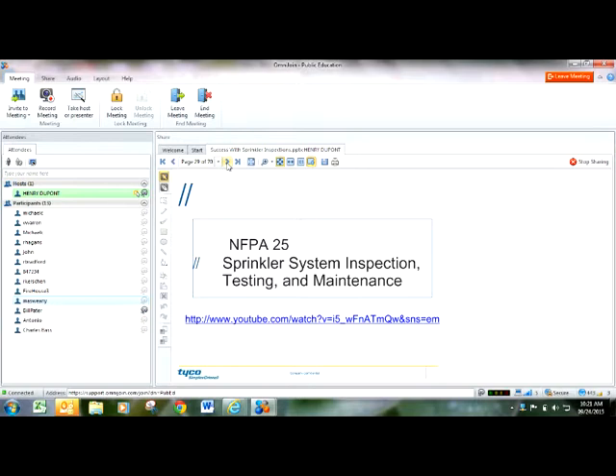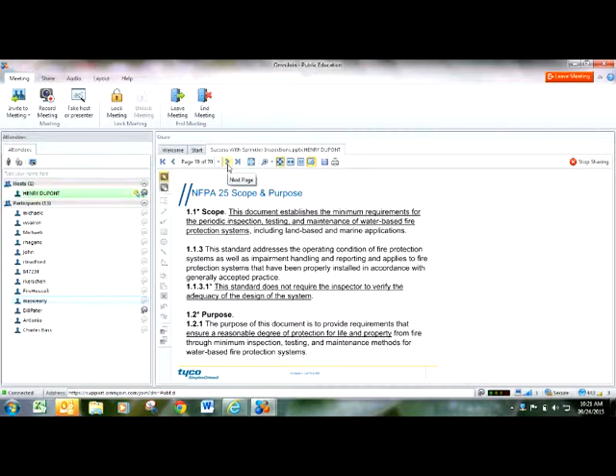So the owner's requirements for maintaining the sprinkler system are talked about in NFPA 25. This link here again is NFPA talking about the differences of NFPA 25 versus other standards. It's a good video to watch. But what is the scope and purpose of NFPA 25? This document is established to set the minimum requirements for periodic testing, inspecting, and maintenance on water-based fire protection systems. The standard does not require the inspector to verify the adequacy of the design of the system, and the purpose is only to ensure a reasonable degree of protection for life safety and property. And that's not NFPA 13, this is NFPA 25 based on inspections.